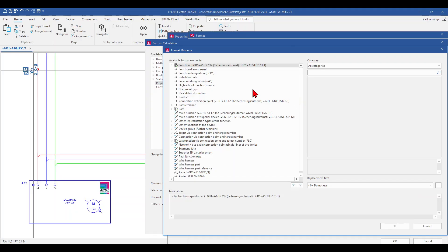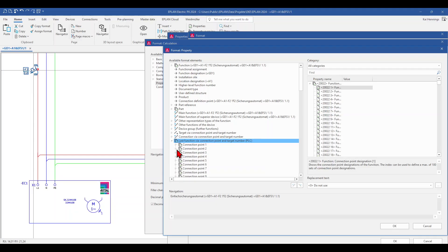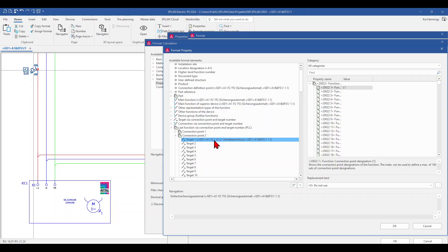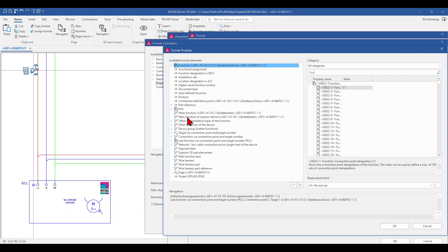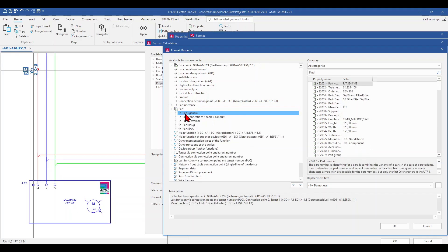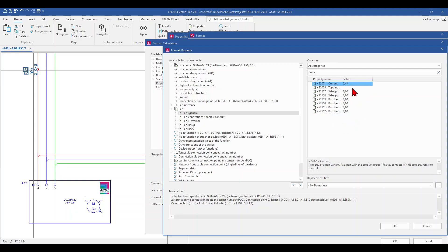So we move it to the right side, and now we want to jump to our Rittal device. We go to the last function via connection point and target number, and connection point 2. Connection point 2 is the lower connection of the MCB, and you can see that target 1 is our X1L1 on EC1. Luckily, in the newer versions of EPLAN we can see the result, so you can see where you are. We want to go to the next level, so now we are on this connection point, then we go to the main function and go to the next level.